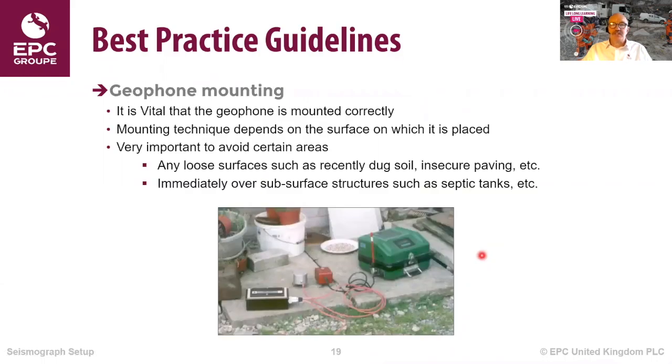Geophone mounting, this is a really important part and quite commonly done incorrectly, and you will then get a high reading or higher reading than you needed to. So the mounting technique depends upon the surface on which you're placing it. It's very important to avoid any loose surfaces such as recently dug soil, insecure paving stones. In fact, I would recommend not using paving stones.